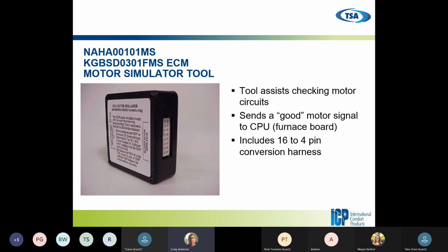So this tool assists in checking the motor circuit. It sends a good motor signal to the CPU, the furnace board. It includes a 16-pin and a 4-pin conversion harness, depending on what motor we're looking at. So this little piece is going to help you. You plug it in, it's going to send a good signal to the board. If the board is getting a good signal, then it's going to tell you if we have a faulty board.